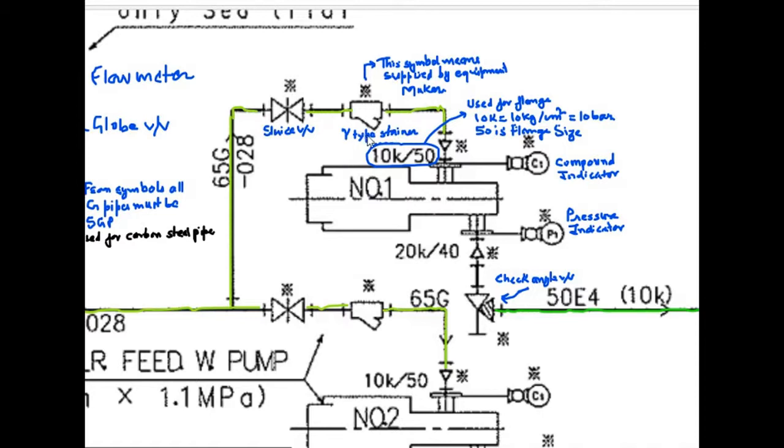Y type strainer is given. Now, one thing is written. You can see 10K 50. This symbol is used for flanges which can withstand pressure of 10 bar. 10K means 10 kg per centimeter square. And 50 is flange size. It is not the diameter of flange. Flange size is different. There is a chart in which you can find the various specification of the flange.